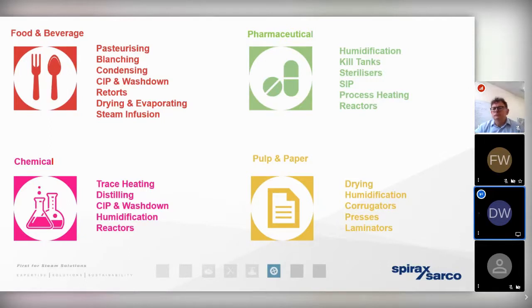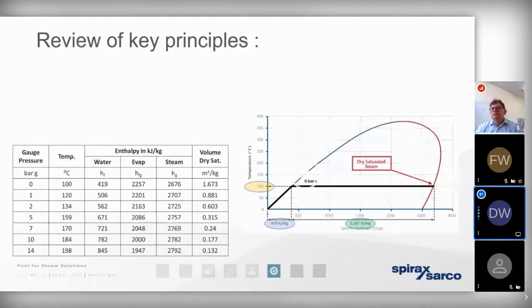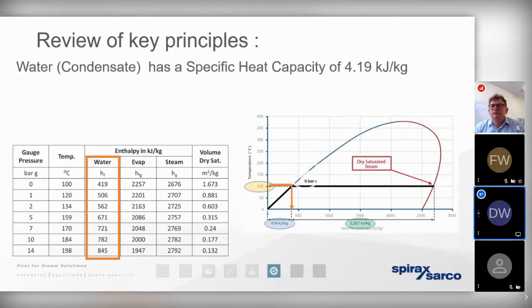And this is a slide that we've shown previously, and it really does bear repeating, because before we can move on to look at the solutions that are currently under development that can help steam be generated and utilized more efficiently, we need to understand the basic properties of steam that are going to form the cornerstone of how those various solutions are able to work efficiently. So the key piece of information that is demonstrated on the steam tables is that water, which is the raw ingredient of a steam system, has a specific heat capacity of 4.19, which ultimately means that if we want to increase 1 kilogram of water by just 1 degree, we need to add 4.19 kilojoules of energy to it.